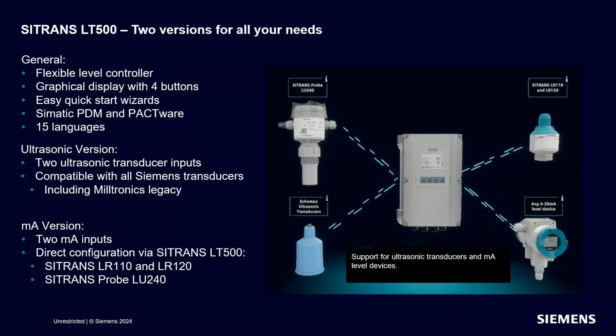In addition, they have a separate version now where you have to pre-order it this way, where you would get 2 milliamp inputs. And one of the unique features is if you pair the LT500 with either the LR110 or the LR120, which are both low-cost radar transmitters, and or a probe LU240, which is a lower-cost self-contained ultrasonic transmitter, using the 4 push buttons on the LT500, you can configure all those devices.